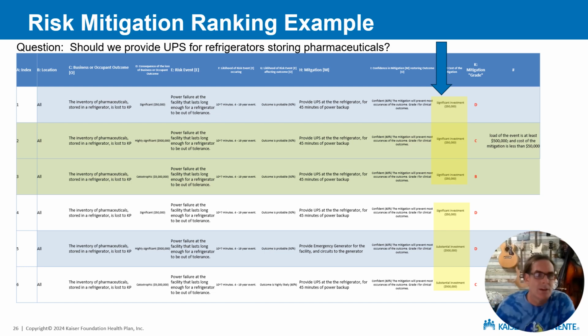And you can kind of see the outcomes, right? If the cost of the mitigation is held down to that sort of $10,000 or $50,000 level, then we get a C and a B when we get to those levels of pharmaceuticals above $500,000 and up to $5 million. On the other hand, if we have the $500,000 investment, then there's almost no way that we can get a passing grade on this score. So this is how we made the decision. We wrote a standard that said if the refrigerator is storing more than $500,000 in pharmaceuticals, then it's justified to add a UPS to that refrigerator, provided that the cost stays down in that $10,000 to $50,000 neighborhood, right?